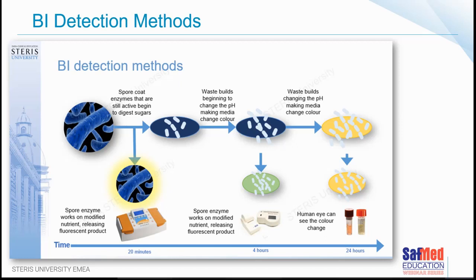In the older days, it was less complex. It was really mostly there to warm up the spores and the growth media together. Now it's required to read light and to measure. So it's very different. It's a more complex design, the incubator, and tends to cost a little more than the other ones used to.